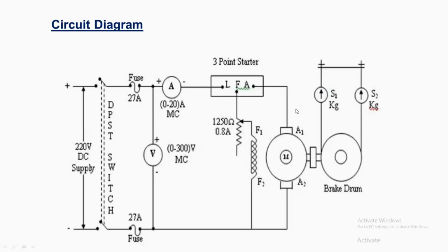When the load increases, the load current increases. So when you take the reading, at the same time look at the ammeter. When you increase the load, look at the ammeter and correspondingly increase the load in steps up to or near the full load rated current. Step by step, measure the readings.